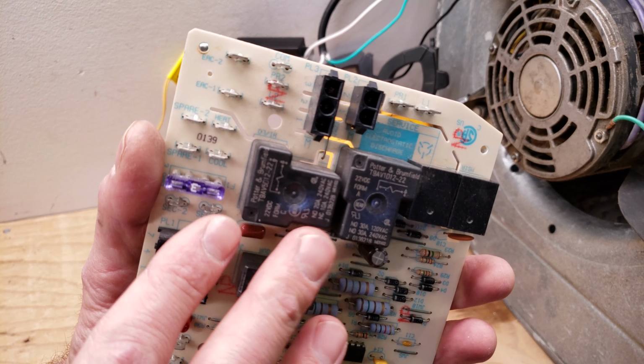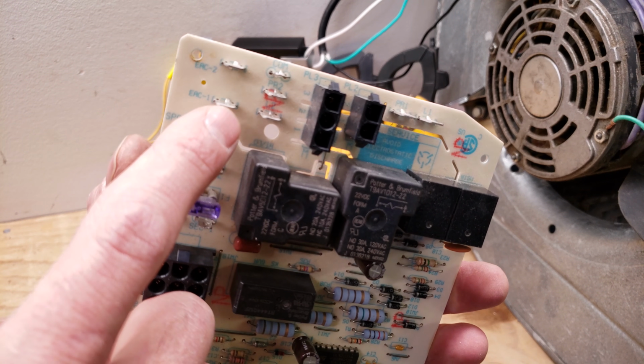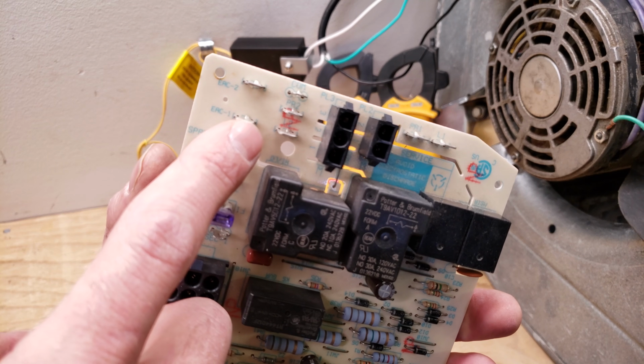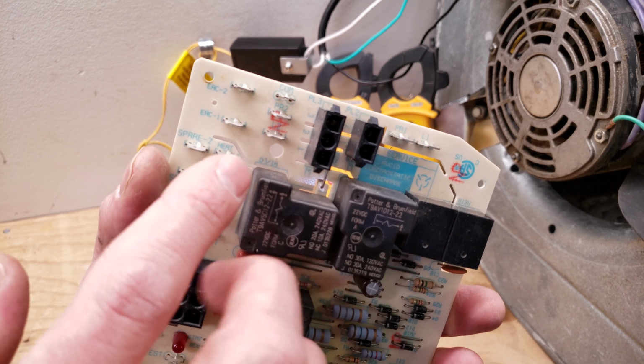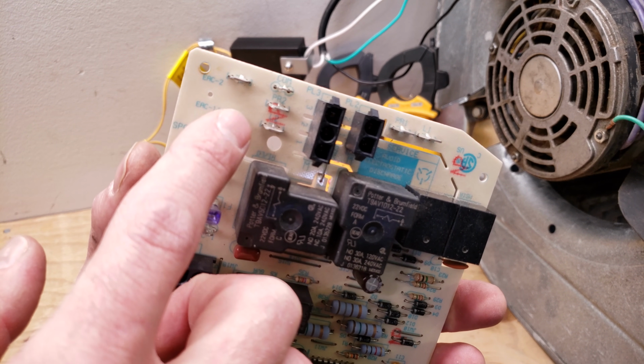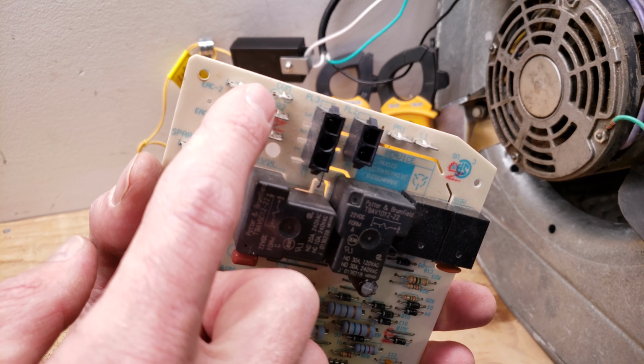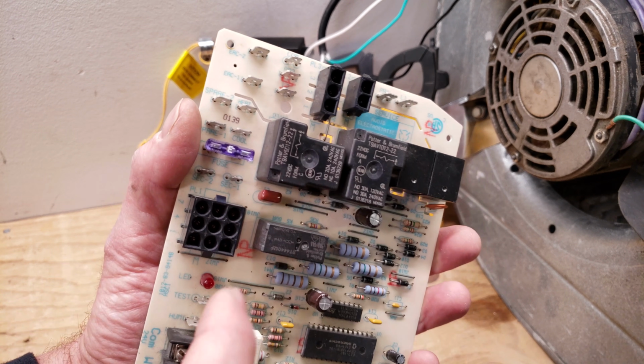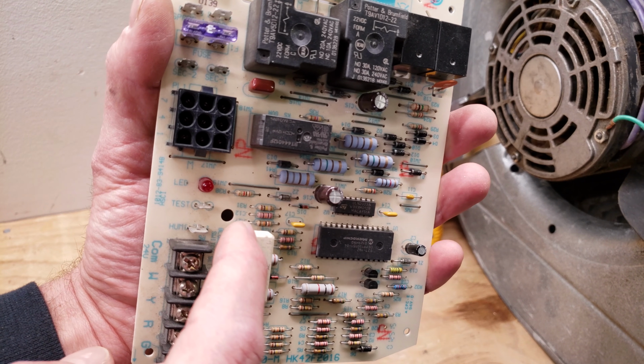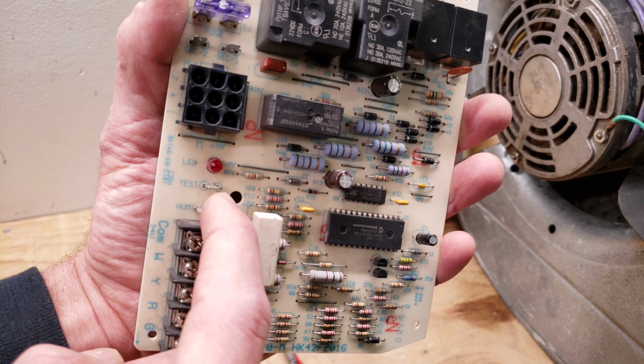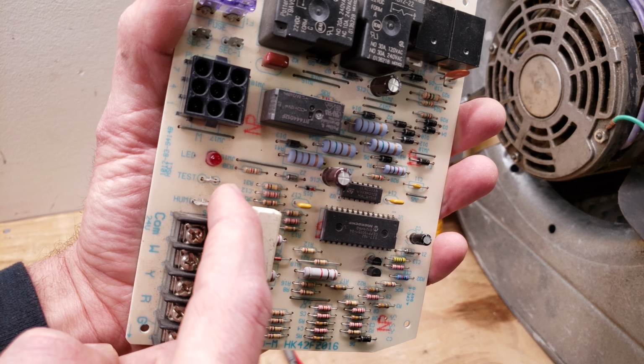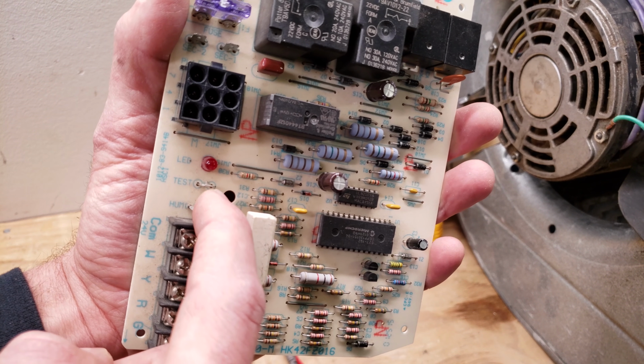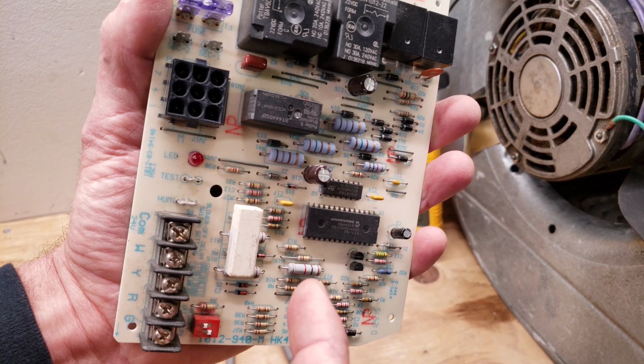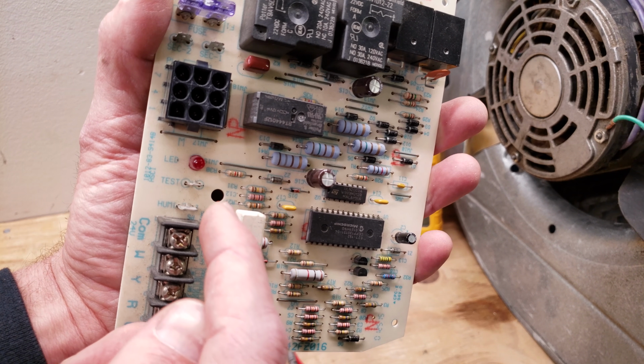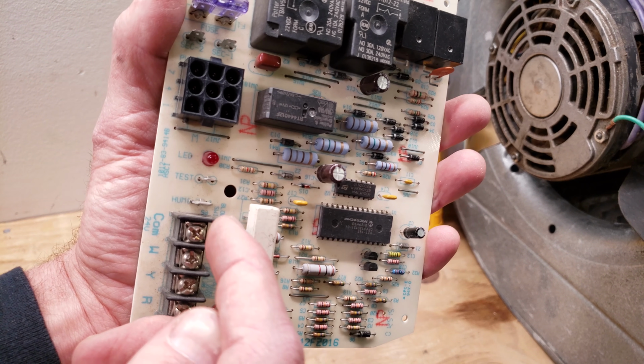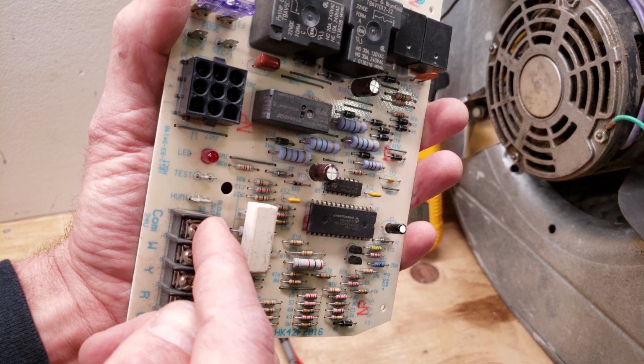Remember that with the new control boards, typically you're going to have EAC terminals in order to power an electronic air cleaner already on the board. So this is EAC1, that's your 120 volt power, and that's your 120 volt common, your EAC2. And then also you typically have a humidifier tap on the board as well. So that's HUM, H-U-M. So this will be the 24 volts off of the board to power the electrical solenoid. And of course you're going to have the humidistat there to break the 24 volt wire going to the solenoid. Your common is your path back.